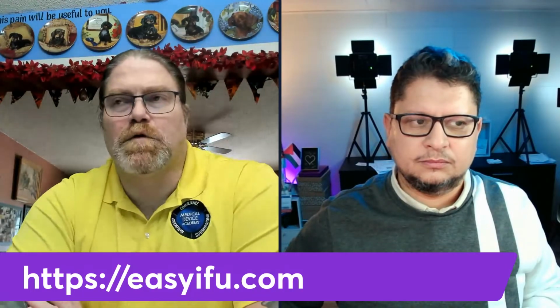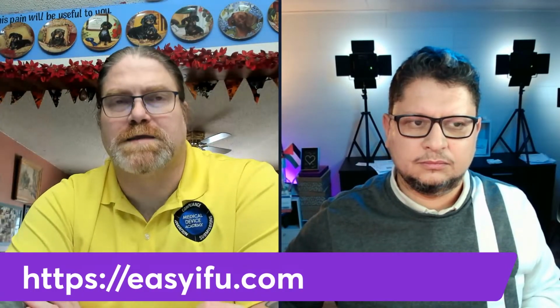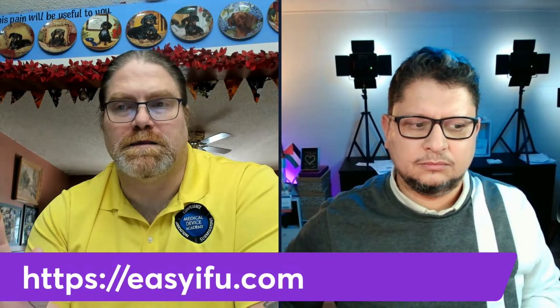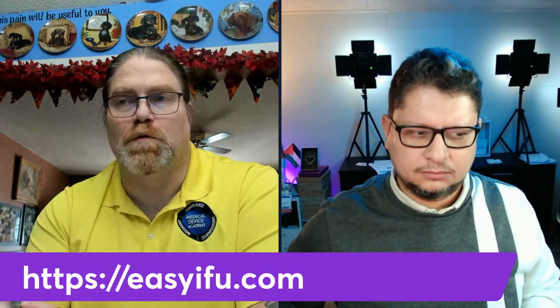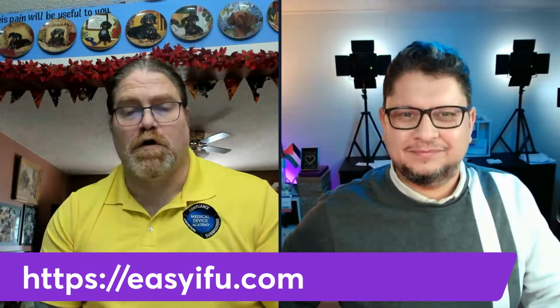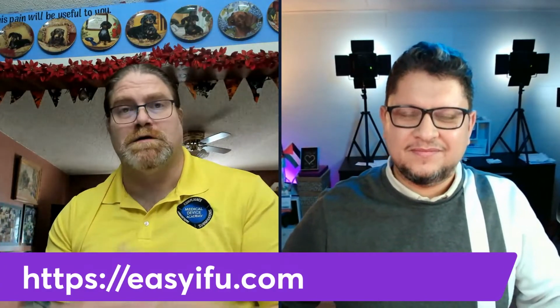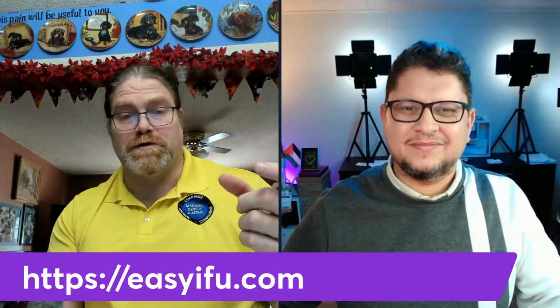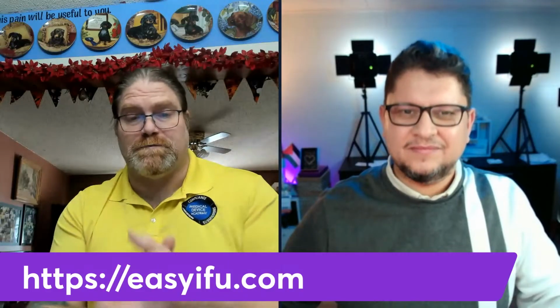I have quite a few different European clients, and they have their own questions about labeling and IFUs. One of the common questions is, how do I do a label for software as a medical device? And I explained to them that on the About page or the splash screen, when you first open the product, you normally will see the name of the product, the version of the product, the address, the manufacturer. That's the label. Exactly.